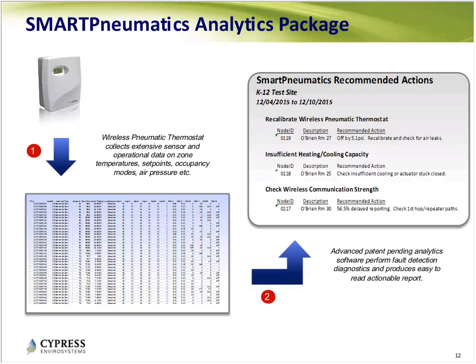So, based on a lot of requests from customers, we developed a software tool that mines the data. We collect data on zone temperature, set points, occupancy modes, and air pressure, as you can see in this slide, and then we crunch it through our analytics engine, and it comes out as 2 types of reports. One is a more prescriptive report, like recalibrate this thermostat, go check this damper to see if it's stuck, or go check for an air leak here. So for people who really have no time to dig deep, we just provide a prescriptive list: go check this thermostat, go to this room, check this node - that's the prescriptive list.